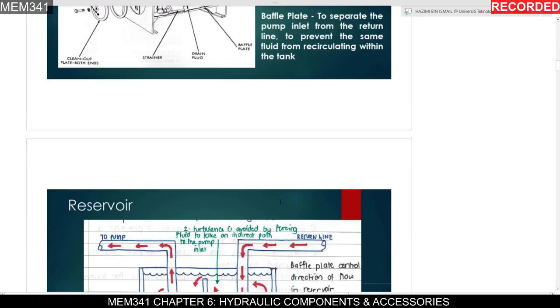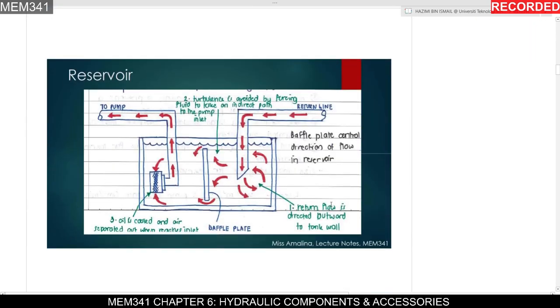Details about the baffle plate can be seen in this diagram, drawn by Miss Amalina. The baffle plate separates the liquid that returns from our actuator or hydraulic pipelines, and when it separates that, it can prevent the return liquid from directly supplying the supply line here to the pump. So the baffle plate acts as a separator between two types of oil or fluid here.